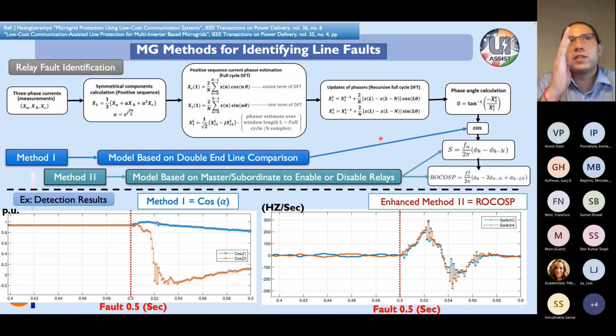And we can be changing, so the last measurement goes out and the new measurement comes in. So we move in this way to improve the speed of the calculation, so we are able to detect in real time if we do have a fault event or any disturbance in the operation of the distributed generation or the microgrid.